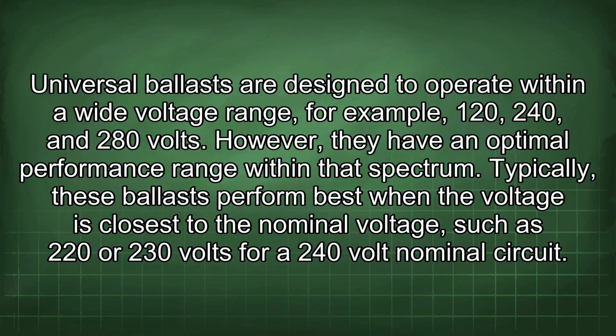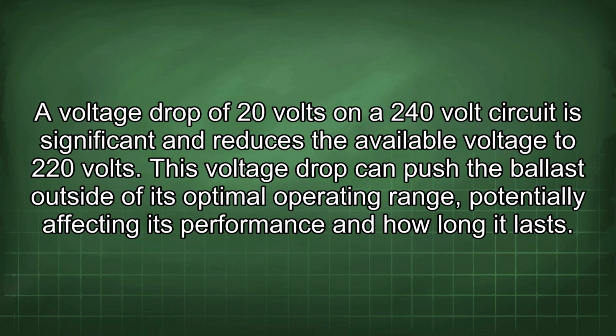Universal ballasts are designed to operate within a wide voltage range, for example, 120, 240, and 280 volts. However, they have an optimal performance range within that spectrum. Typically, these ballasts perform best when the voltage is closest to the nominal voltage, such as 220 or 230 volts for a 240 volt nominal circuit. A voltage drop of 20 volts on a 240 volt circuit is significant and reduces the available voltage to 220 volts.